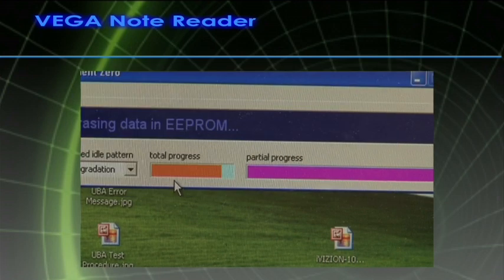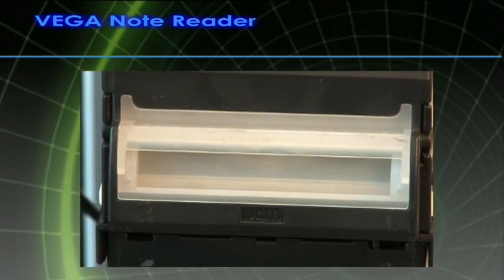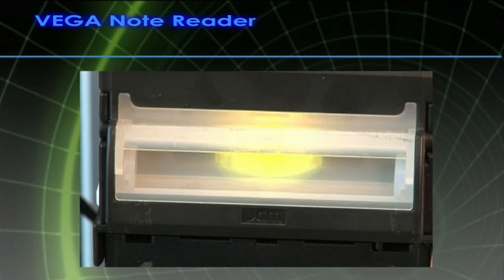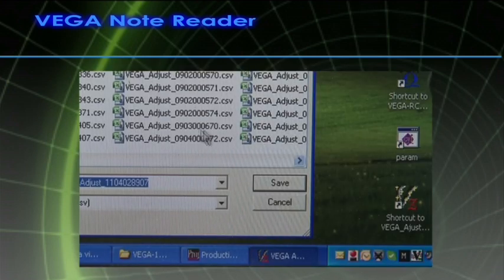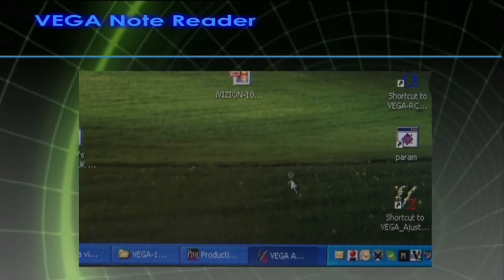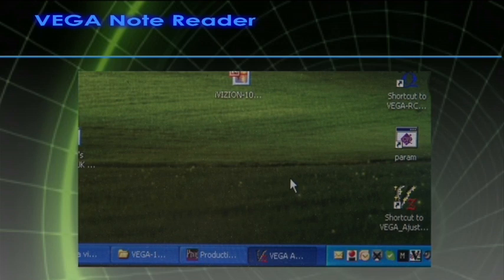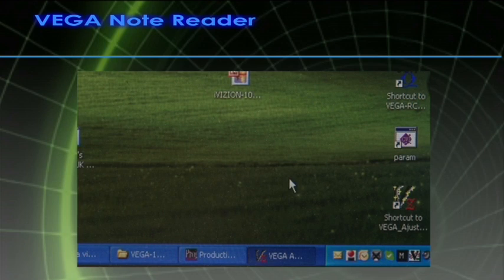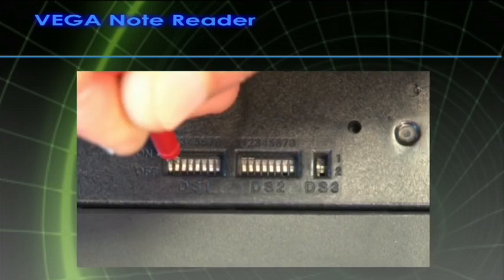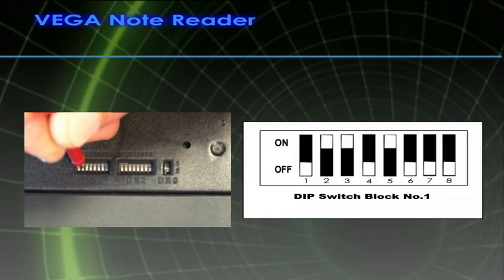As you press the Yes button, the unit will be activated and will flash the yellow light. Then a new window asks you to store the calibration data in EEPROM. Press Yes to store the data on your PC, or press No to complete the calibration without saving the data. Once the calibration is complete, reset the dip switches to the normal positions. Switches 2, 3 and 5 to the off position.